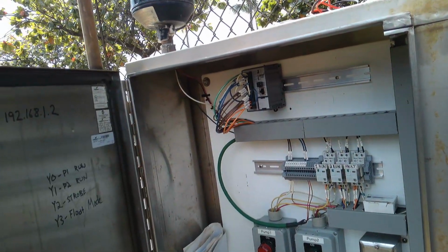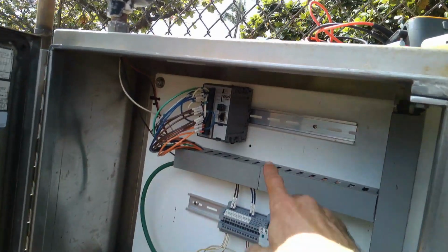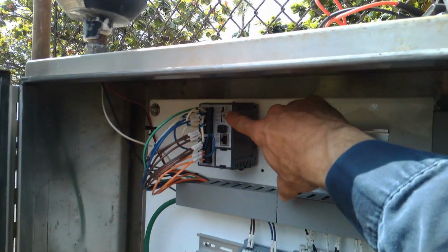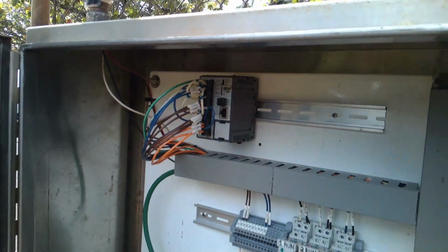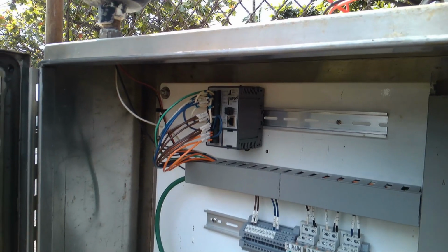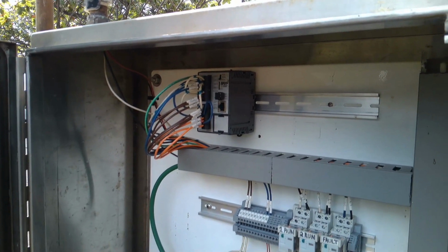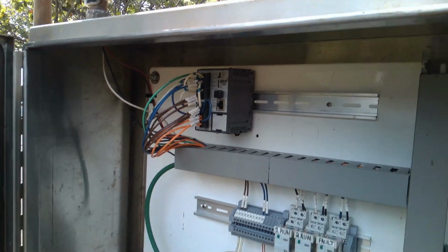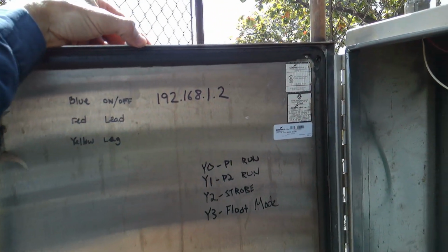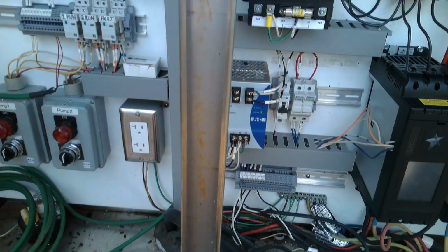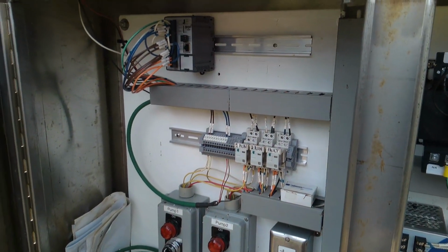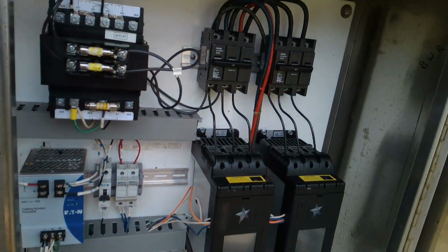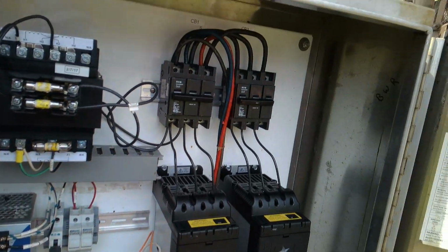Then the other thing I noticed before I powered anything up is on our BRX PLC, it is currently in stop mode, which I don't know why anyone would change that. Maybe the operators thought to put that down. So yeah, we'll go ahead and power it up and see if we can get the same fault behavior to occur, and then start running through our checks, see what's going on.